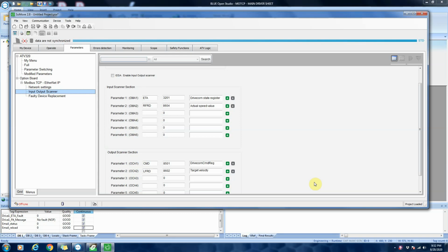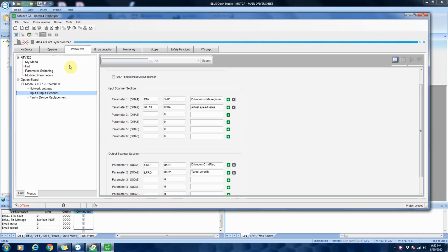In this video, we're going to show how to read fault status and what the actual faults are from an Altivar 320 or an Altivar 630 from Schneider Electric into a Modicon Unity PLC. The first thing we need to do is pick a drive that has Ethernet. So in this case, we used a 320 drive. We have the same capability out of the 630 and 930 series.